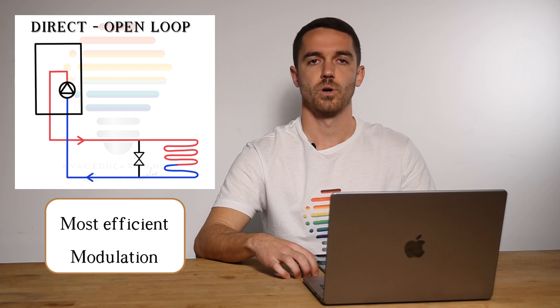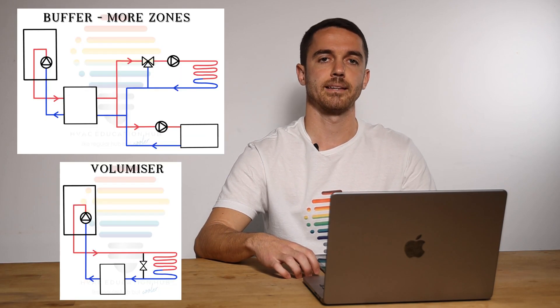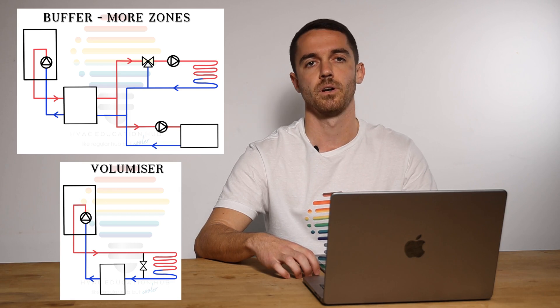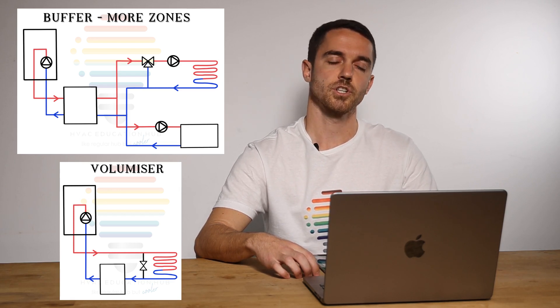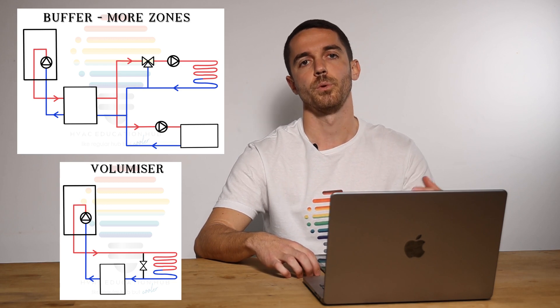We will try to explain not only by theory, but by examples with site visits and analysis to see what is the best solution. If you have a direct system and you don't have a buffer — even as a volumizer — you need to ensure that your system is an open loop system, so you need all zones open. In that case, your zones act as a big buffer tank. This is mostly important if you have fan coils, because fan coils have bigger pressure drop and lower water volume. In that case you will probably need a buffer tank, even as a hydraulic separator or return switch, especially in cooling, because cooling requires the unit to operate at low temperature and you need a large water volume.